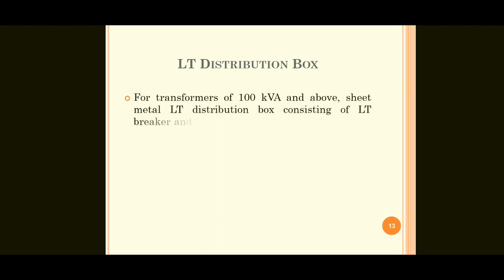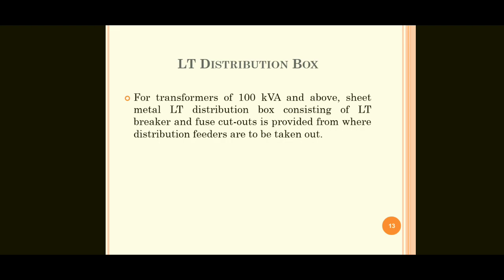Next one, LT distribution box for transformers of 100 kVA and above. Here transformers are usually rated in terms of kVA, not in terms of kilowatts, because the rating depends only on voltage and current. Copper losses depend on current and iron losses depend on voltage. That's why the rating is expressed in kVA, meaning kilovolt ampere, instead of being tied to power factor.